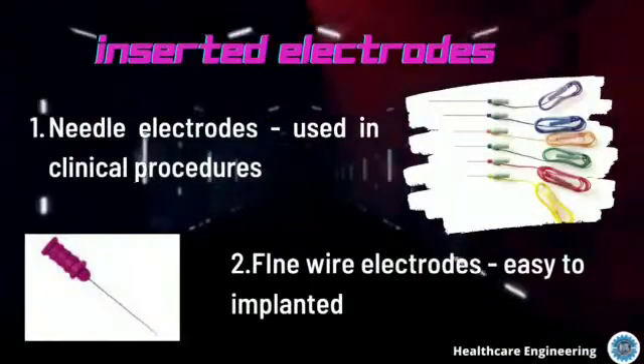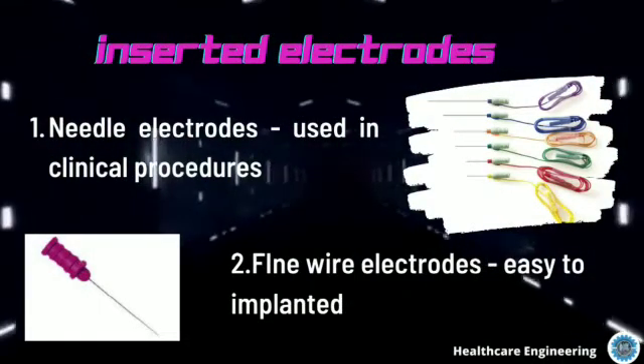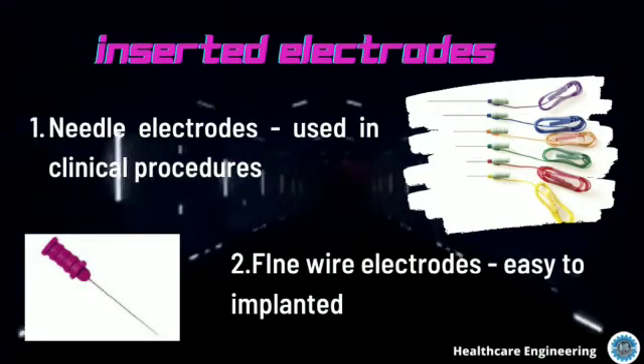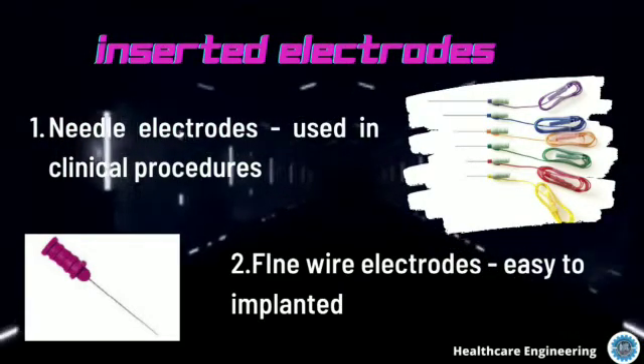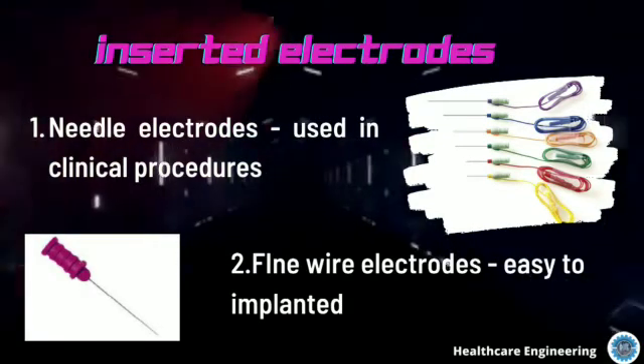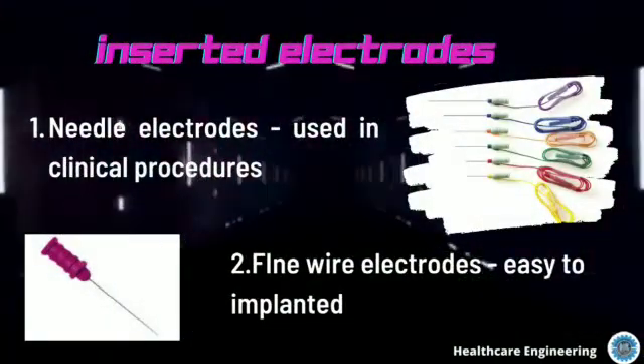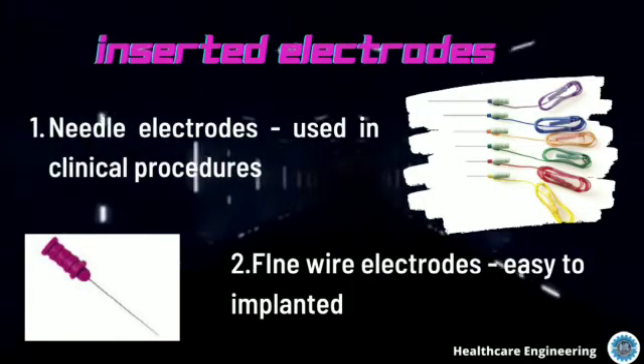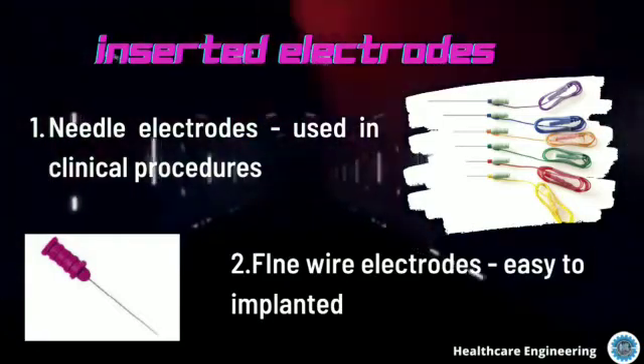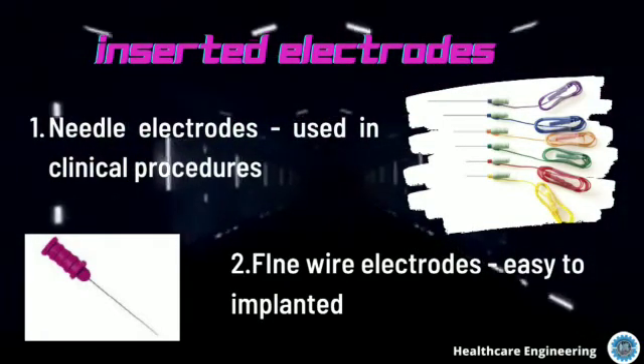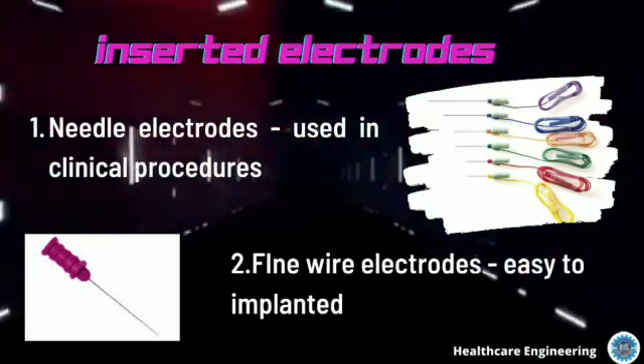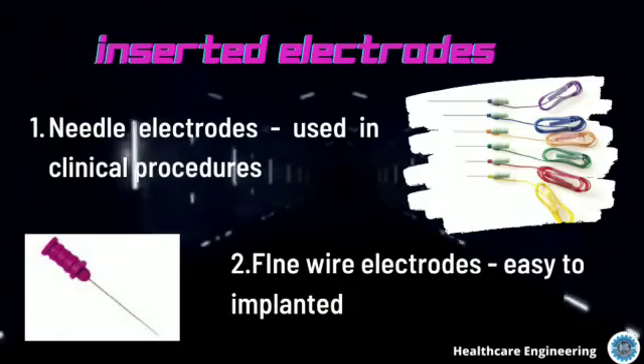Inserted electrodes have two further types: needle electrodes and fine wire electrodes. Needle electrodes are widely used in clinical procedures and neuromuscular evaluations. The tip of the needle electrode is bare and used as a detection surface, and it contains an insulated wire in the cannula. Fine wire electrodes are made from small diameter, highly non-oxidizing stiff wire with insulation. They are easily implanted and withdrawn from skeletal muscle, and are generally less painful than needle electrodes, whose cannula remains inserted in the muscle throughout the entire test.